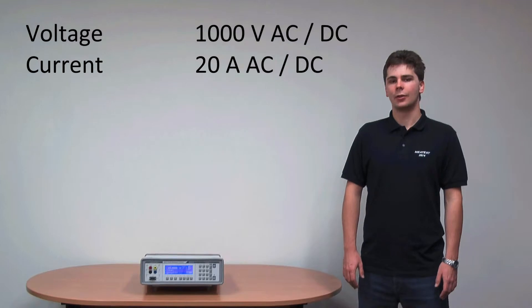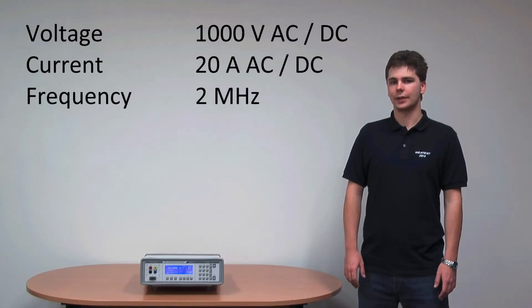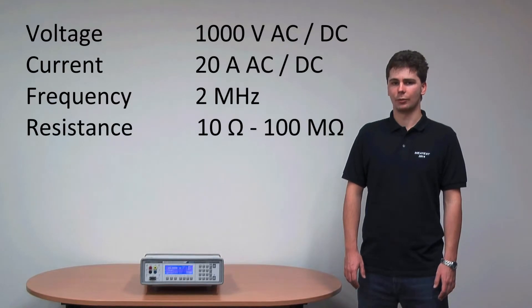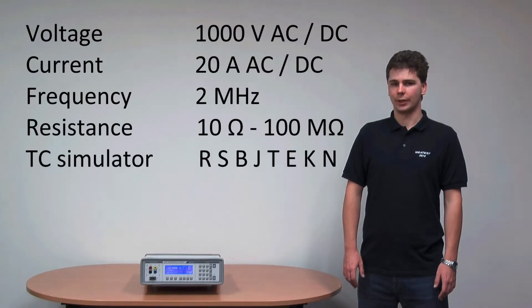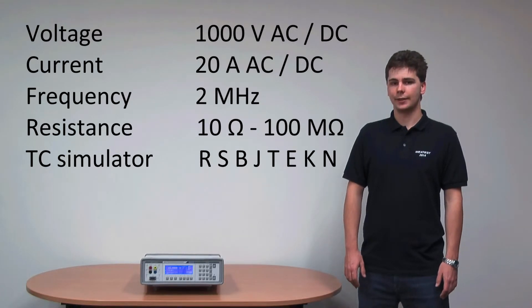Other inbuilt functions are frequency generator up to 2 MHz, fixed resistors in 10 Ohms to 100 MOhms range, thermocouple simulator with cold junction compensation and optionally an RTD simulator.